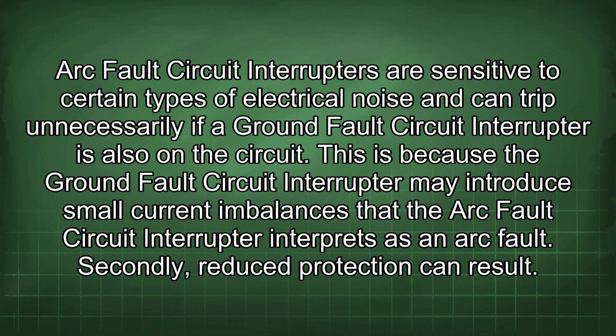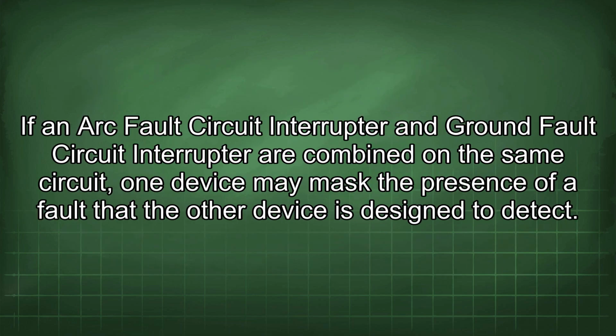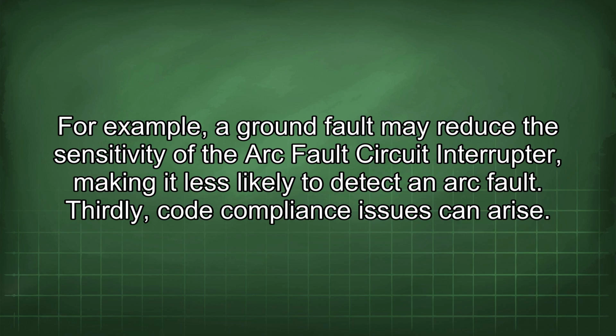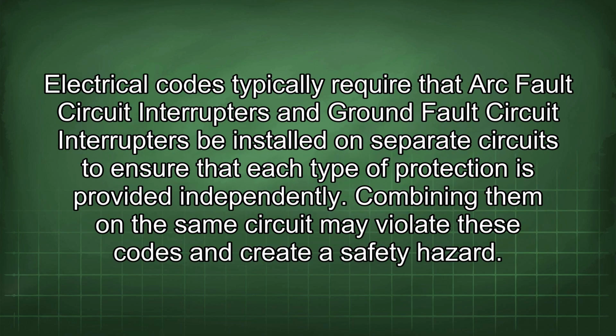This is because the ground fault circuit interrupter may introduce small current imbalances that the arc fault circuit interrupter interprets as an arc fault. Secondly, reduced protection can result. If an arc fault circuit interrupter and ground fault circuit interrupter are combined on the same circuit, one device may mask the presence of a fault that the other device is designed to detect. For example, a ground fault may reduce the sensitivity of the arc fault circuit interrupter, making it less likely to detect an arc fault. Thirdly, code compliance issues can arise. Electrical codes typically require that arc fault circuit interrupters and ground fault circuit interrupters be installed on separate circuits to ensure that each type of protection is provided independently. Combining them on the same circuit may violate these codes and create a safety hazard.